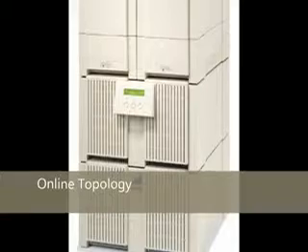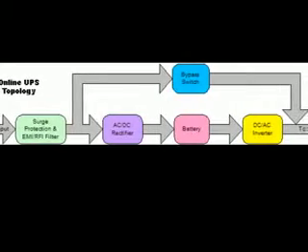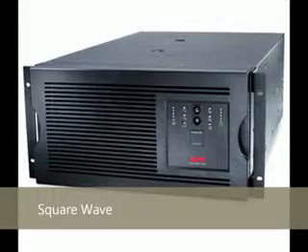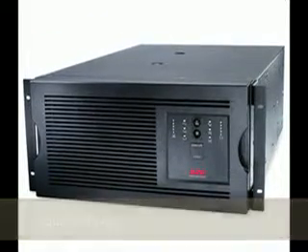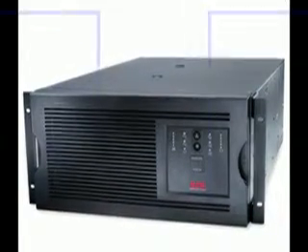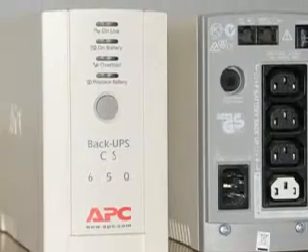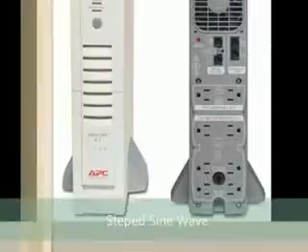The on-line topology is designed so that continuous power to the load is made through the DC/AC inverter. The square wave inverter waveform is suitable only for power devices that have their own internal power supply. The step sine wave inverter attempts to simulate a true sine wave.